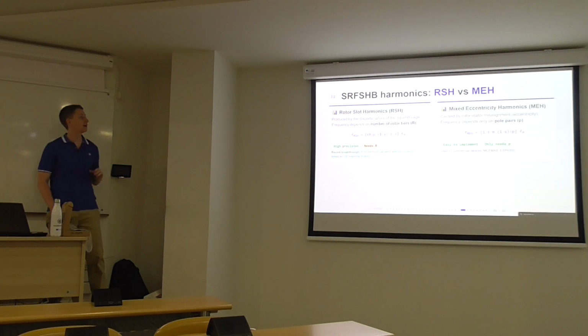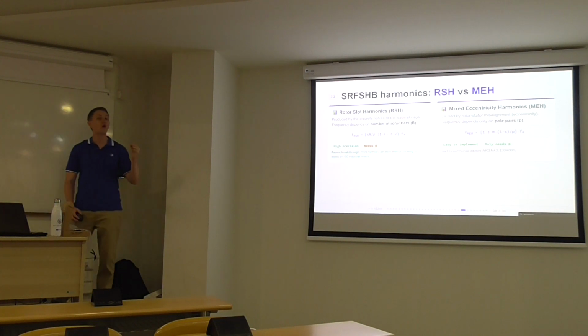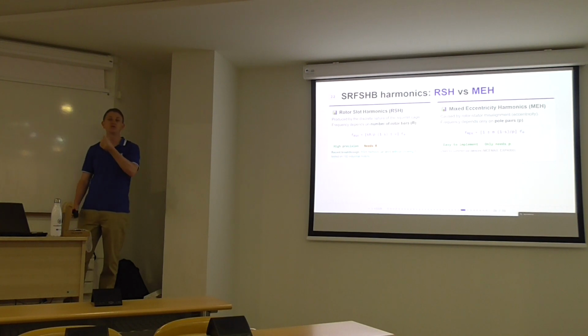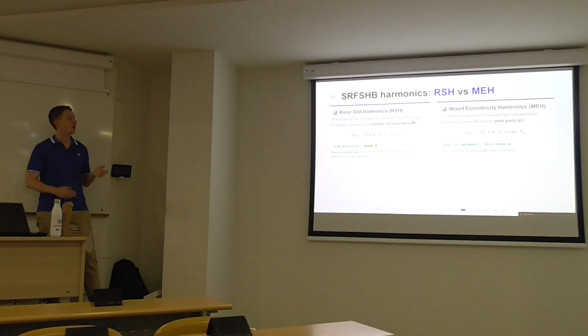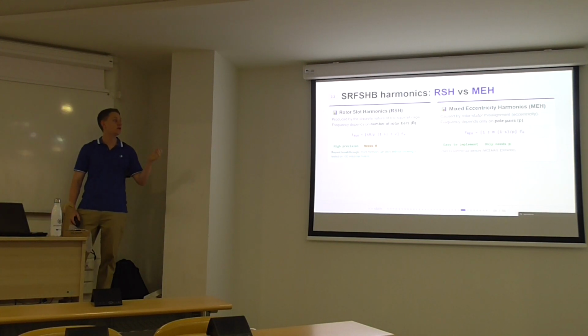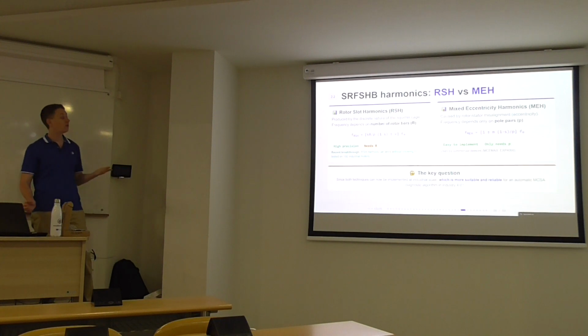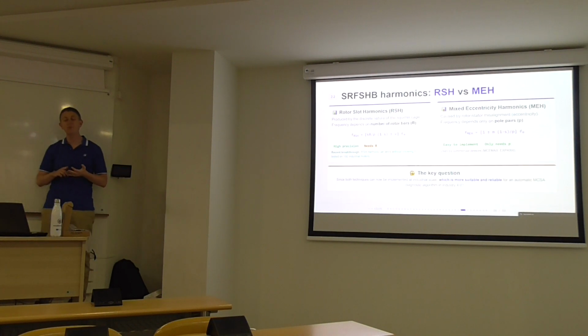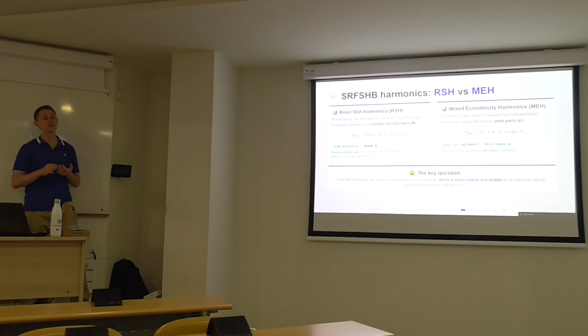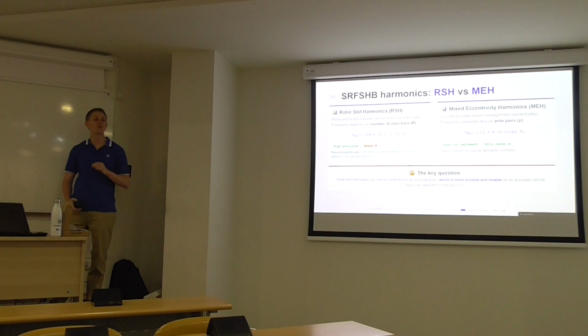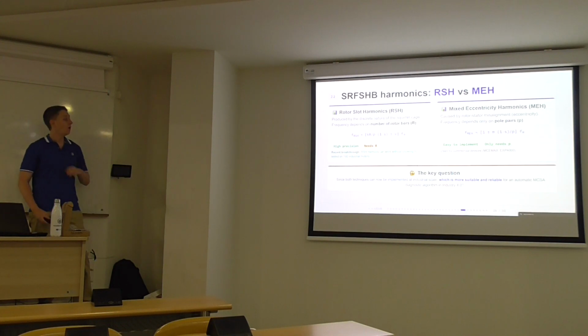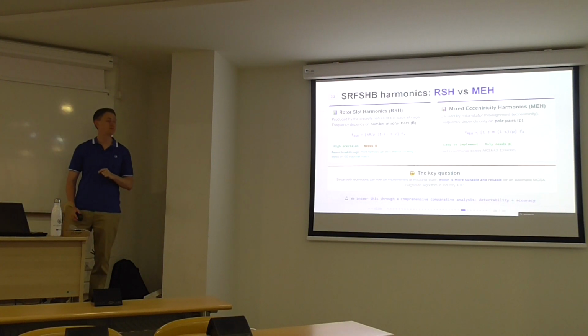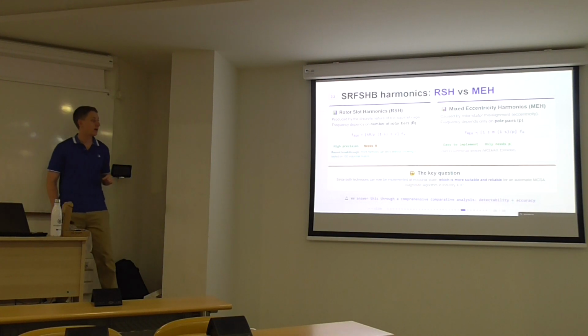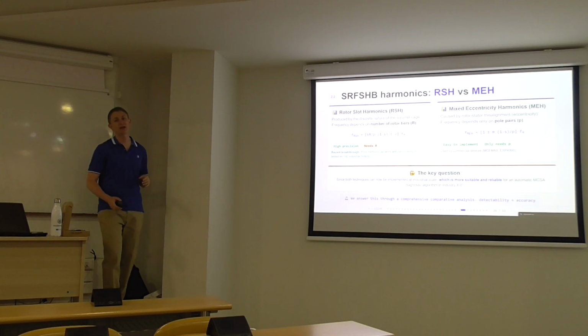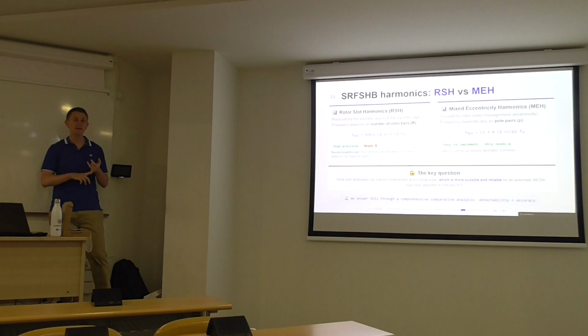And then we have the mixed eccentricity harmonics, which are caused by rotor stator misalignment, okay, eccentricity. And the frequency depends only on the number of pole pairs. You can always know the number of pole pairs from the nameplate data. So that is the reason why they have been used traditionally in commercial devices. But now there's a key question that arises. Since both techniques can now be implemented at industrial scale, which is more suitable and reliable for automatic MCSA algorithm? Well, we have answered this question in our recent paper, okay, where we have analyzed both harmonics from 2 points of view, from detectability and accuracy.